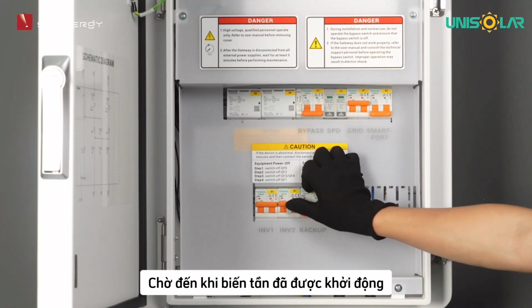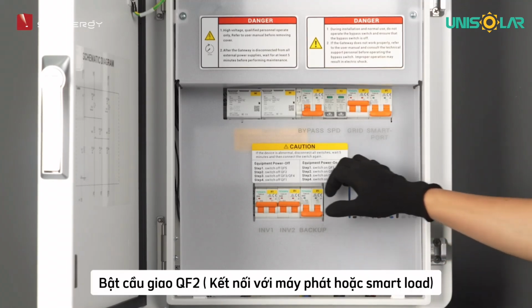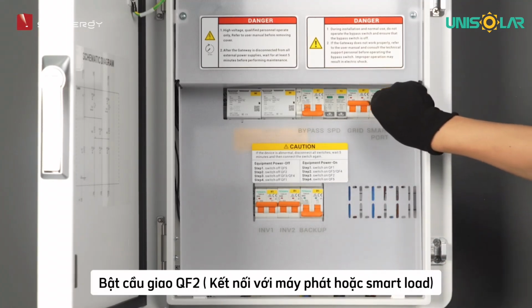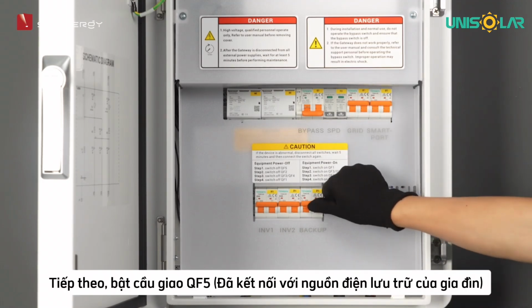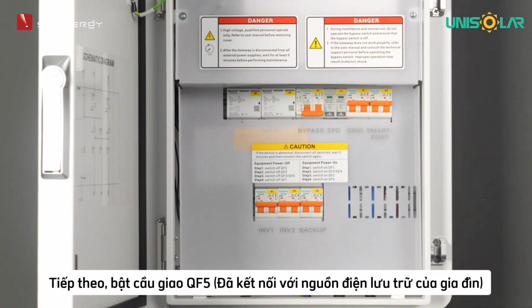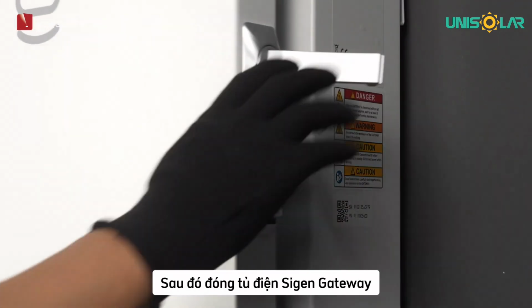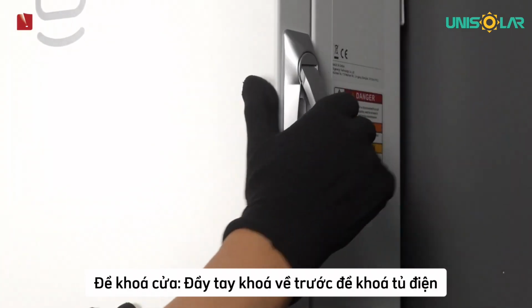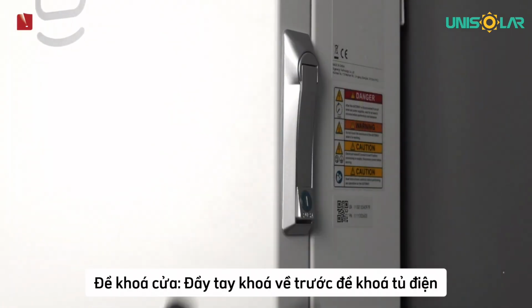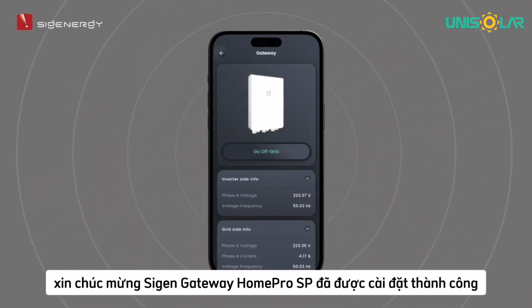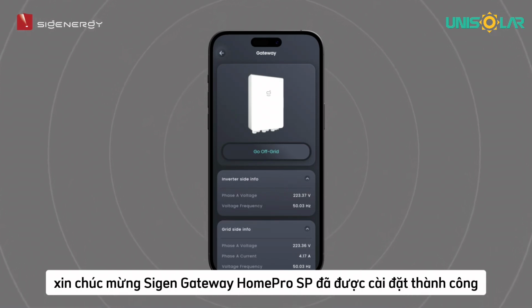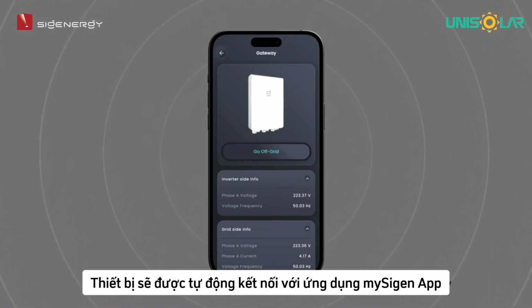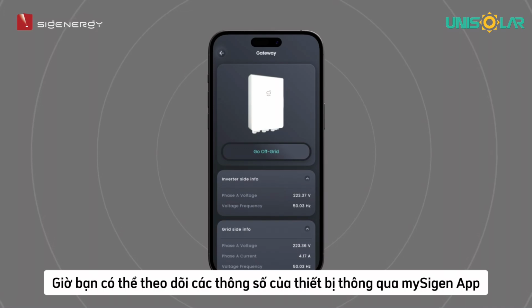Wait until inverter is powered on. Turn on the miniature circuit breaker QF2, connecting to a generator smart load. Turn on the miniature circuit breaker QF5, connecting to a backup household load. Finally, close the equipment door. Close the door and push the lock forward to fasten it. Congratulations, the gateway has been successfully installed. Now you can see in the My Sigen app that the gateway has been automatically connected to the system.